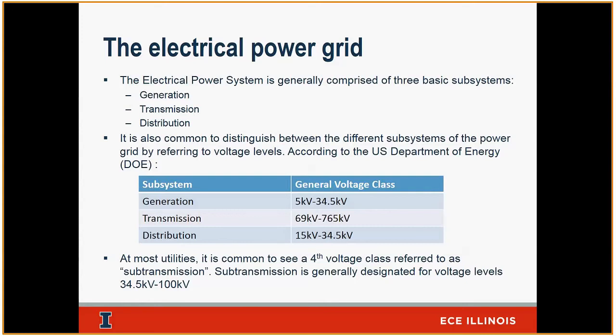And again, load models are different. The topology and power flow mechanisms for each are different. And transmission is a whole different world. The industry is trying to converge and put them all together in one model, all the way from generation to the small customer node on the distribution side. And we'll talk about the advantages of that. The energy now flows as a network, all the way from the distribution system to the sub-transmission system. It never used to do that. So now it calls for a model where I can see and have resolution over the whole spectrum.